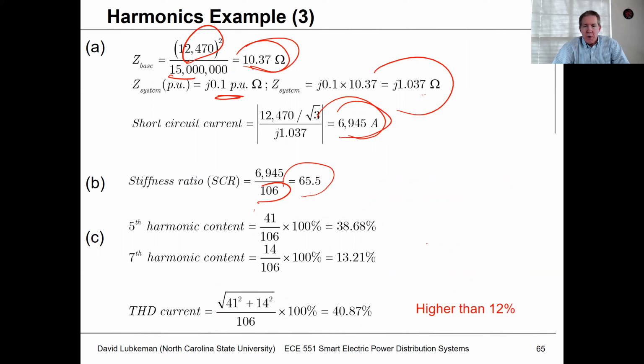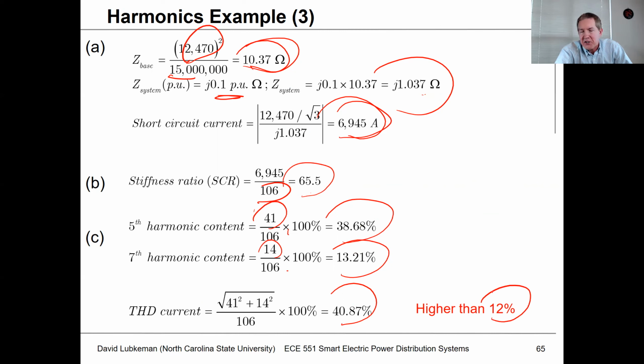Okay, then I can see where we are as far as THD on the currents. If I've got 41 amps at the fifth harmonic and 14 amps in the seventh, I normalize by 106, which is the fundamental, multiplied by 100%. And I got about 39% for the fifth harmonic and 13% for the seventh. If I calculate the THD, you can see I'm at 40.87. And so not only do I have my individual harmonics above the limit, this THD level is way above where I need it to be.